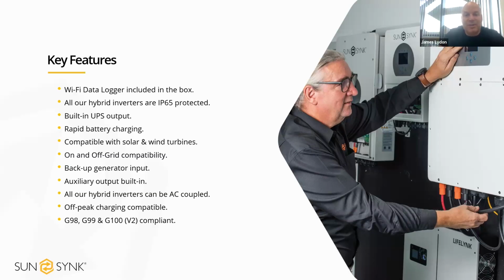All of our inverters are IP65, so no issues with them being installed outdoors. That's the same with the majority of our batteries. All of our inverters have a built-in UPS output, so anything directly connected to the inverter will remain powered in the event of a power cut. So some people might decide to offer a customer maybe just a double socket, or you can split the board. You can have your essentials board and your non-essentials board. So yeah, anything directly connected to that circuit on the load output on the inverter will remain powered.